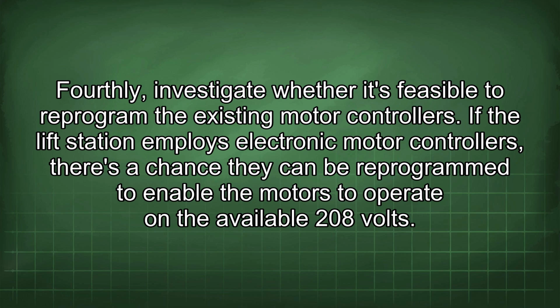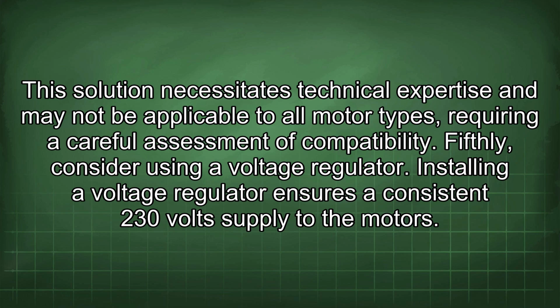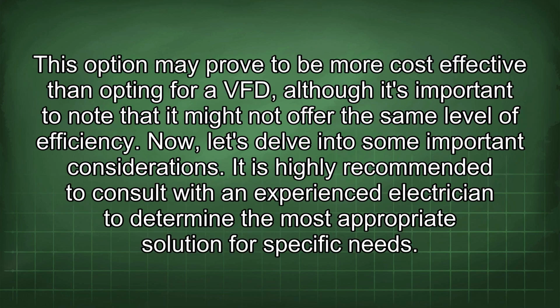If the lift station employs electronic motor controllers, there's a chance they can be reprogrammed to enable the motors to operate on the available 208 volts. This solution necessitates technical expertise and may not be applicable to all motor types, requiring a careful assessment of compatibility. Fifthly, consider using a voltage regulator. Installing a voltage regulator ensures a consistent 230 volt supply to the motors. This option may prove to be more cost-effective than opting for a VFD, although it's important to note that it might not offer the same level of efficiency.